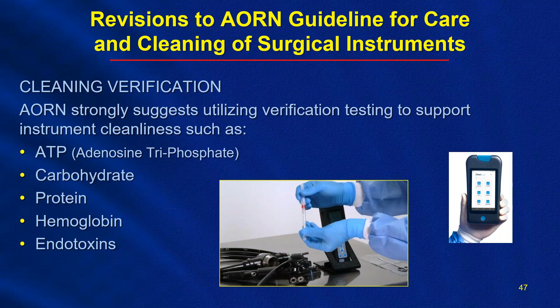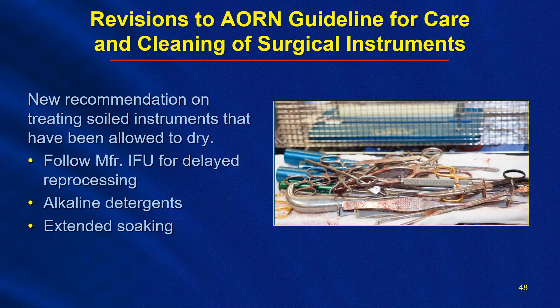They also have a new recommendation on treating soiled instruments that have been allowed to dry. We mentioned earlier in the presentation that instruments that are allowed to dry are very, very difficult to clean. Now manufacturers are coming out with IFUs for what they call delayed reprocessing. So if instruments have been allowed to dry, there may be special recommendations like using highly alkaline detergents to start breaking down and getting the dried bioburden off, extended soaking times and things like that.